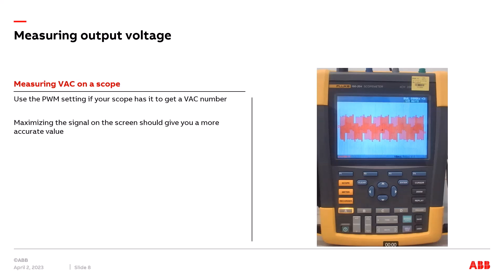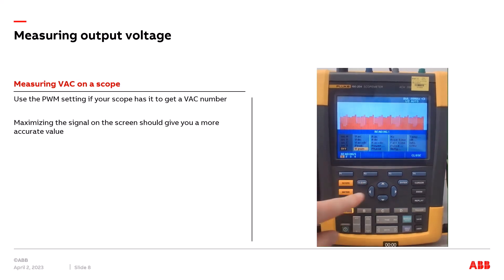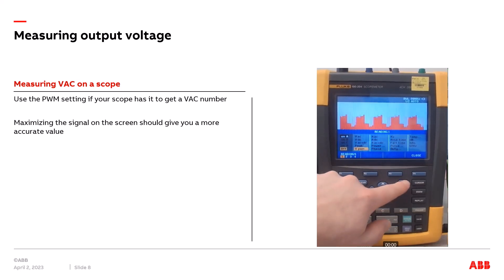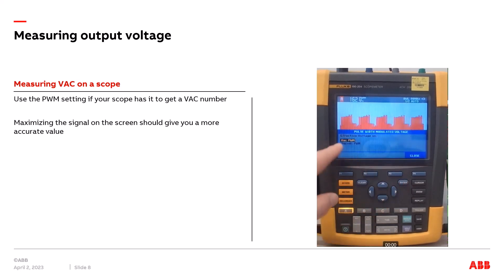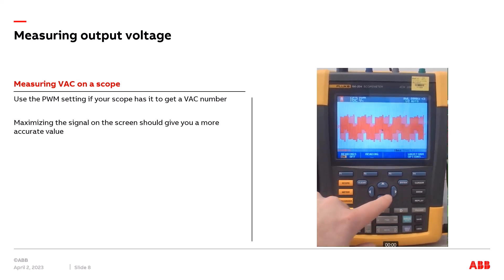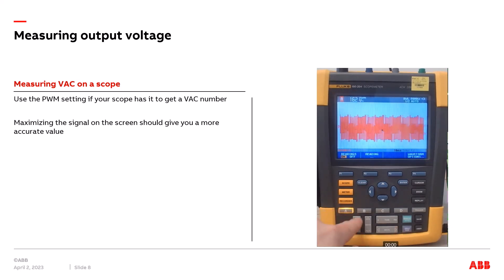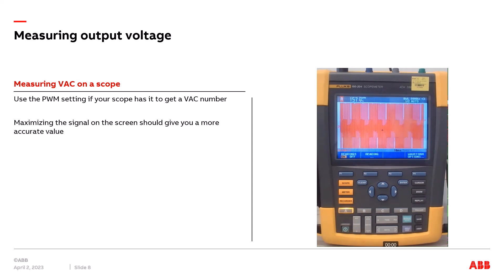Besides output frequency, we can also have the scope tell us the equivalent AC voltage of the signal going to the motor. The VFD uses PWM — pulse width modulation — to recreate the voltage. Ideally, instead of just using voltage AC, use a setting of voltage PWM if your scope has it, as this gives a more accurate equivalent AC voltage. Selecting voltage PWM shows 162 volts; increasing the resolution to maximize the signal on screen gives around 157–158 volts, which more accurately represents the equivalent voltage as displayed on the drive's control panel.